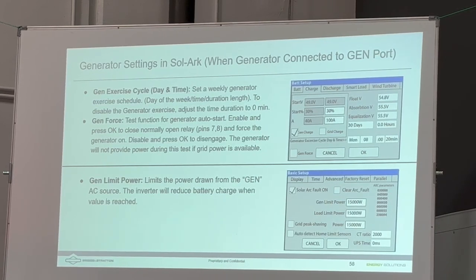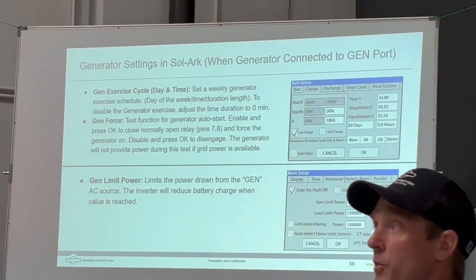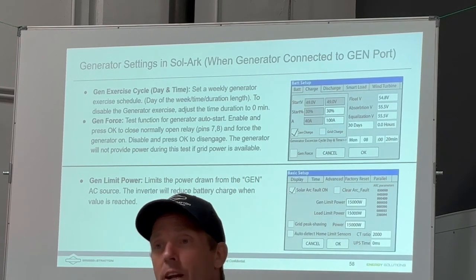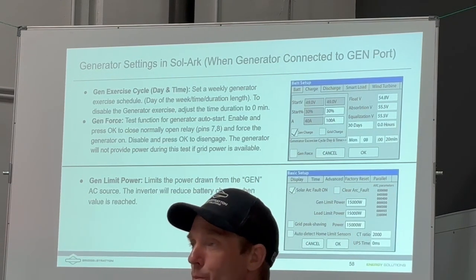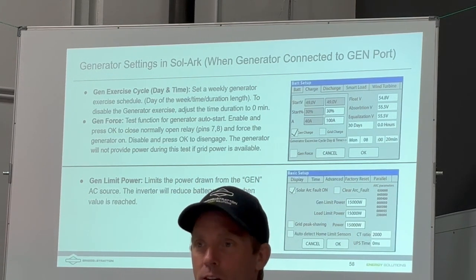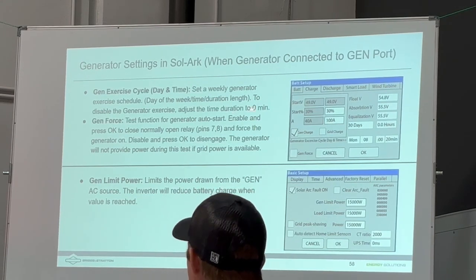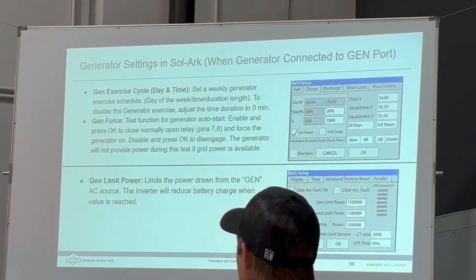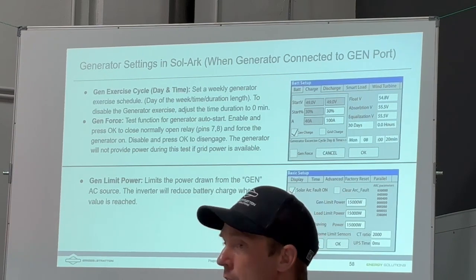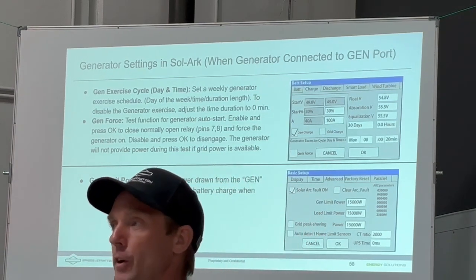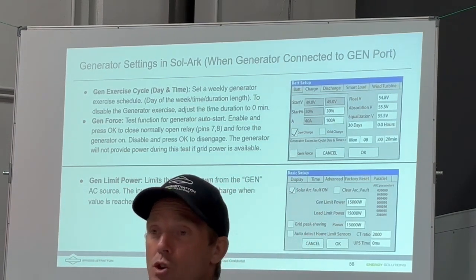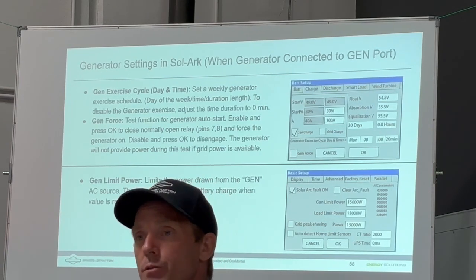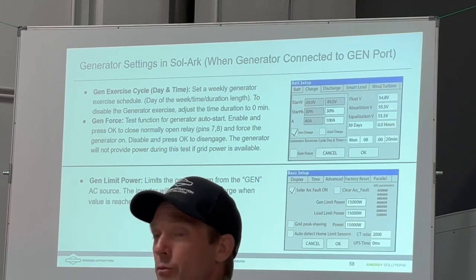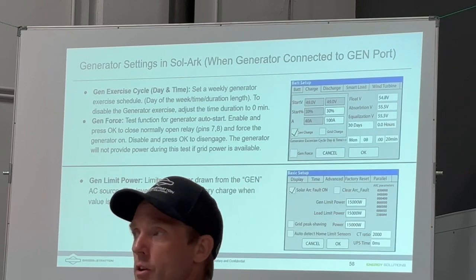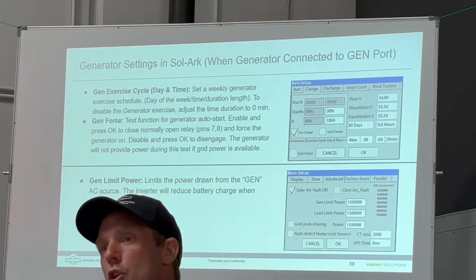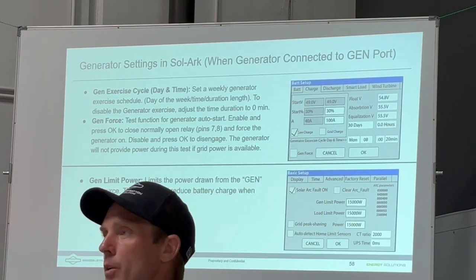So let's suppose I've got a portable generator, just maybe a little 5K portable generator, and I want to bring it into the 15K inverter, which is capable of drawing 100 amps out of it. We can limit how much power the Sol-Ark will allow to be coming out of the generator port. And if I go over that amount of power and batteries are charging, it'll slow down the battery charging rate. Or if it's way more power than the generator can supply, it will start discharging the batteries to supply the extra power that's needed.